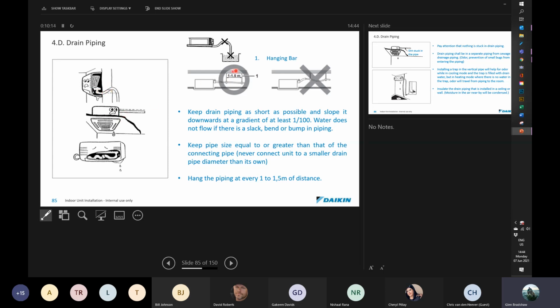Okay, and ensure that you have sufficient fall on your piping. Okay, and no sags. So the piping must be supported at regular enough intervals that the PVC piping that you're using does not sag. Okay, and don't let it start looking like the ocean, because all of these become air traps and eventually you're not going to get the water flowing through it. Okay, so we recommend a 1 to 100 gradient, okay, sloping downhill.